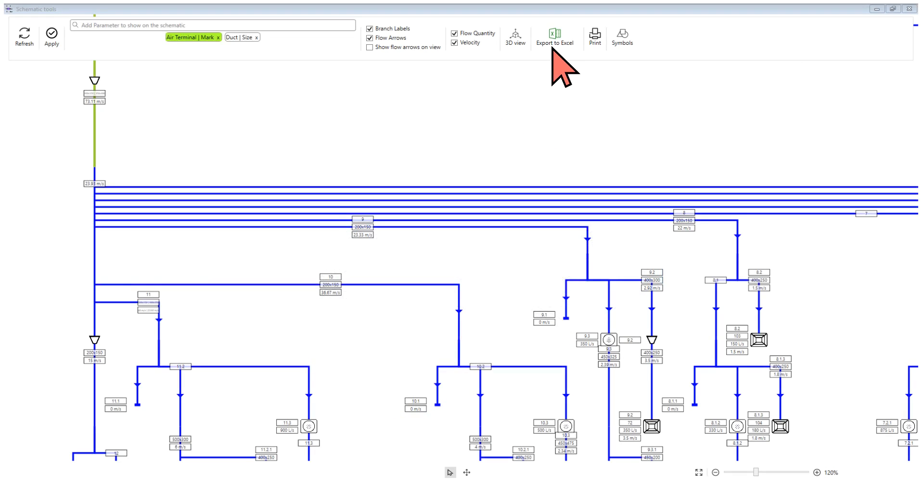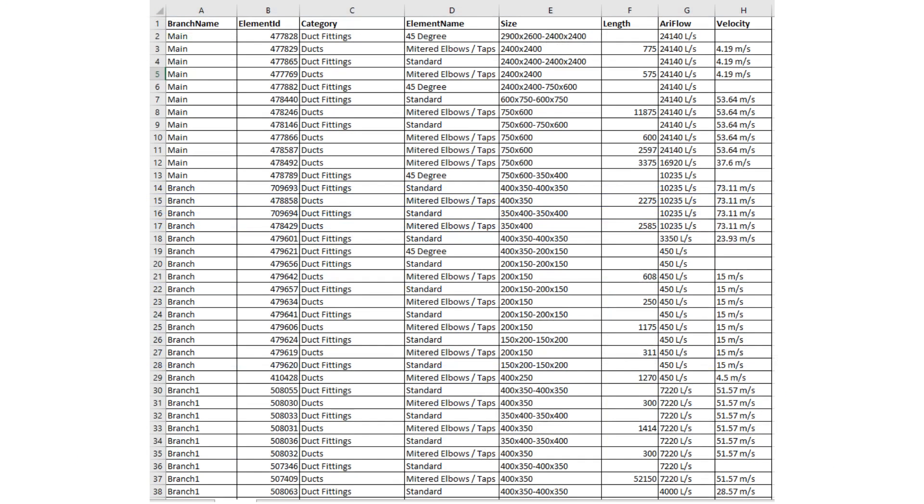If you click on the export to Excel button, an Excel schedule of the system will be exported. The Excel report will include branch name, element ID, category, element name, duct size, and duct length by default. It also adds any other parameter you selected on the schematics.